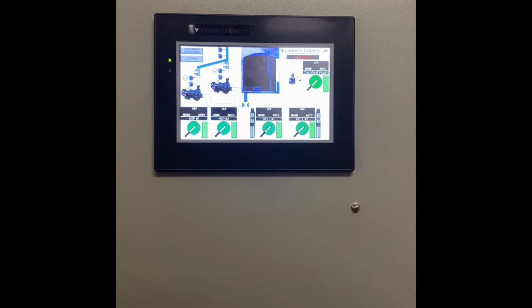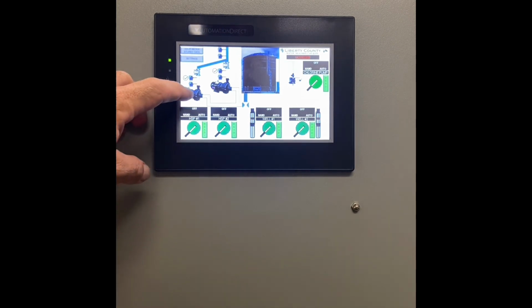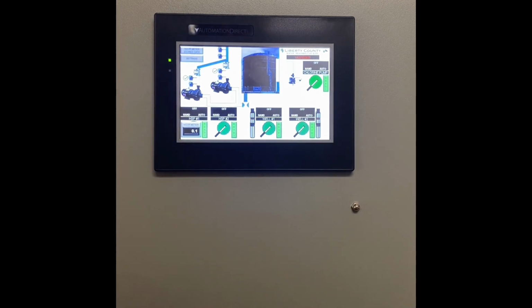Okay, the only thing I haven't talked about is the hour meters that are on this screen. Now you can get them from the hour meter stored data. It's the very top row of data on that screen. But if you want to look at the current data for only high service pump number 1 and you still want to watch to see if well number 2 kicks on for some reason, you can go here and touch and it'll bring up the hour meter. And if you touch it again, it hides back away. All of my pop-up windows use the same methodology. It's a toggle on, toggle off method.